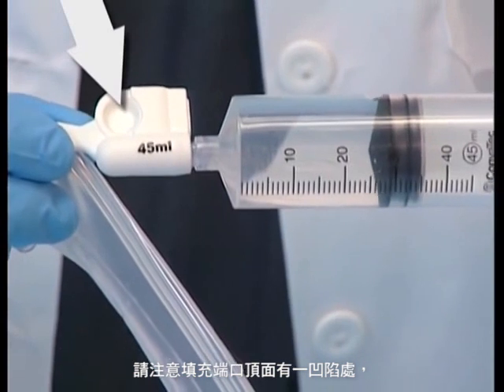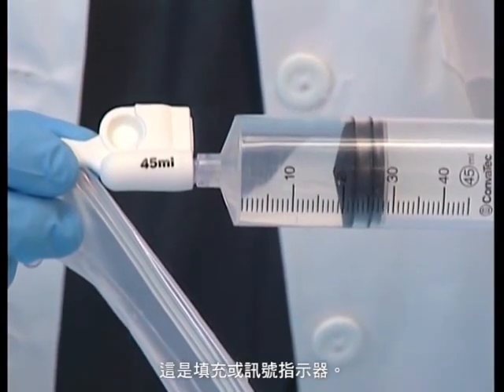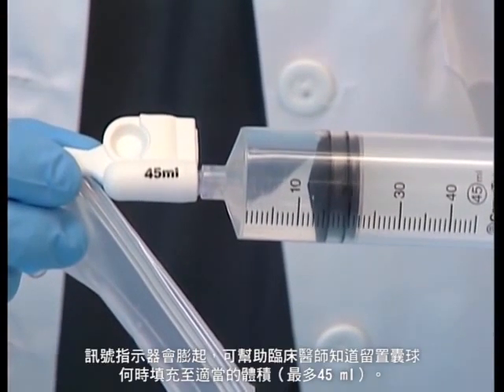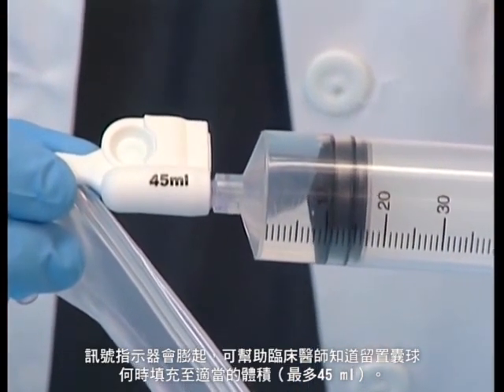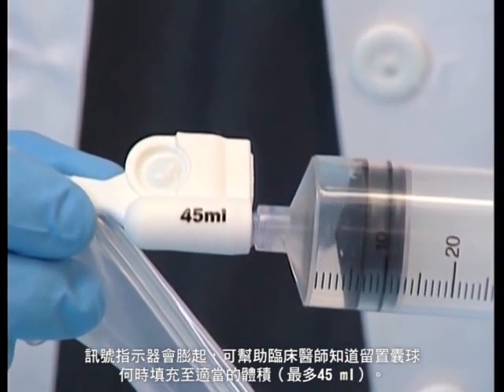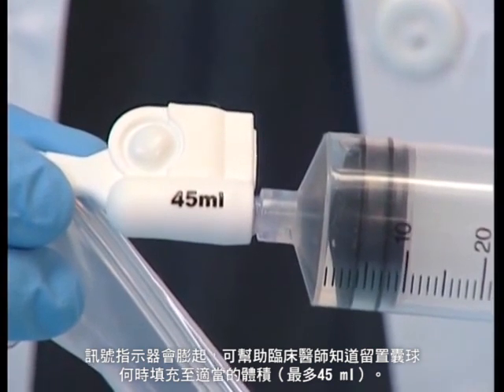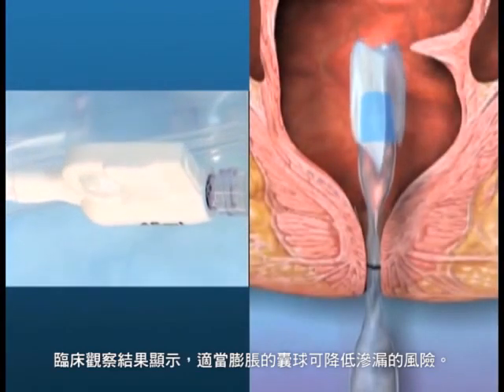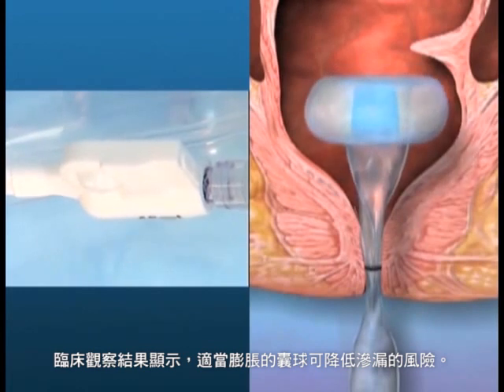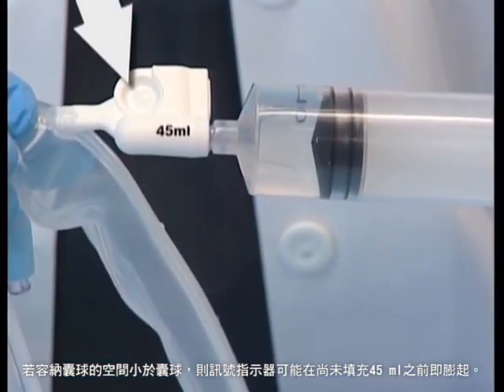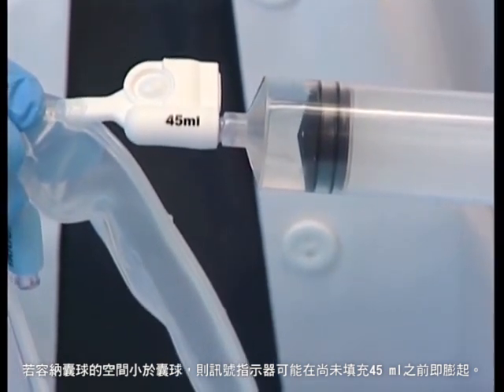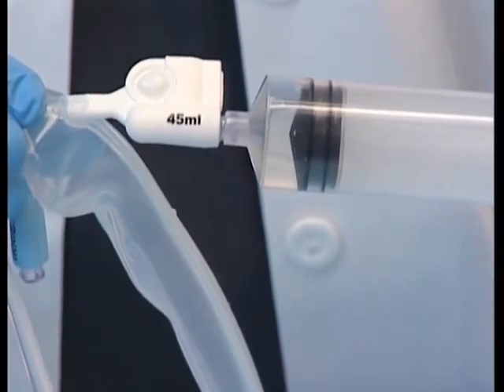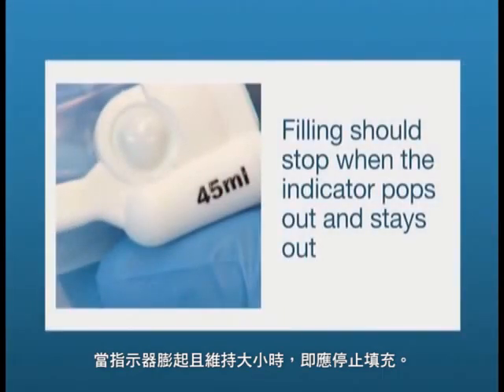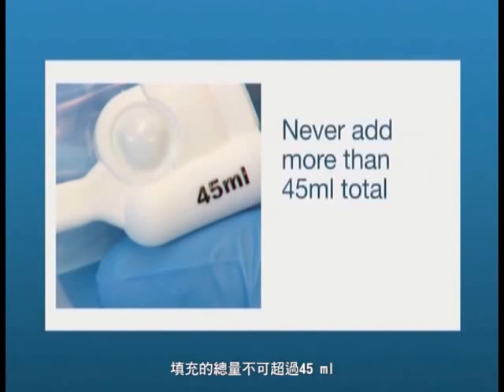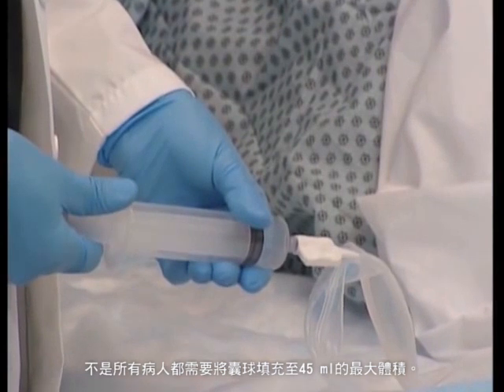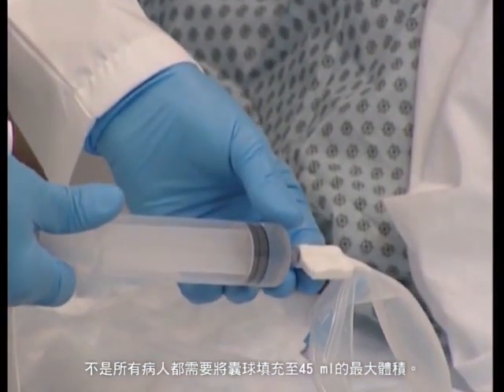Note the dimple or crater on the top of the inflation port. This is the fill or signal indicator. The signal indicator pops to assist clinicians in determining when the retention balloon is filled to the appropriate volume up to a maximum of 45 ml. Clinical observation has shown that proper inflation of the balloon minimizes the risk of leakage. The signal indicator could pop before 45 ml if the space available for the balloon is smaller than the balloon. Filling should stop when the indicator pops out and stays out. Never add more than 45 ml total. Not all patients will require inflation of the balloon to the maximum of 45 ml.